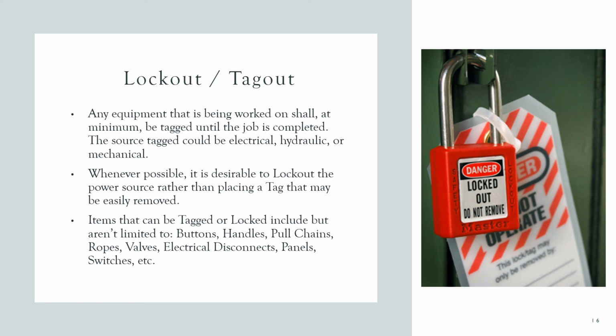So any equipment that's being worked on shall at minimum be tagged until the job is done. The thing you tag could be electrical, hydraulic, or mechanical. Whenever possible, it is desirable to lock out the actual power source rather than just placing a tag that may be easily removed. Items that can be tagged or locked include, but are definitely not limited to, buttons, handles, pull chains, ropes, valves, electrical disconnects, panels, switches, etc.